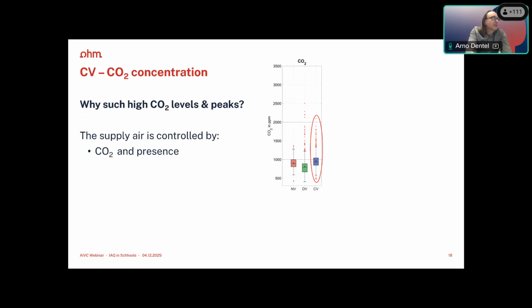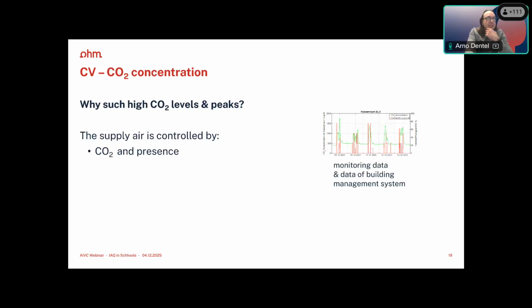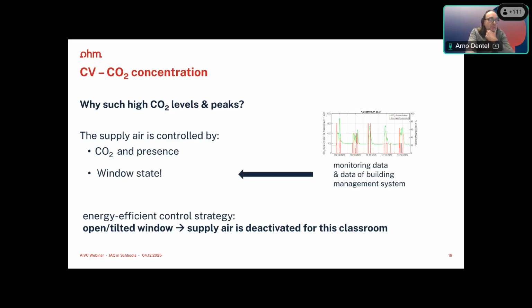In the centralized ventilation system in these two rooms, we observed very, very high CO2 levels and peaks, and we asked ourselves, why is that? And they told us that the system is controlled there by CO2 and by presence sensors. But we also had a look at the monitoring data of the building itself, and we found out that they also observe the window state, and when they open the window, they shut off the mechanical ventilation system. But nobody knew that until this project. So they have no mechanical ventilation during the time that they open one window.